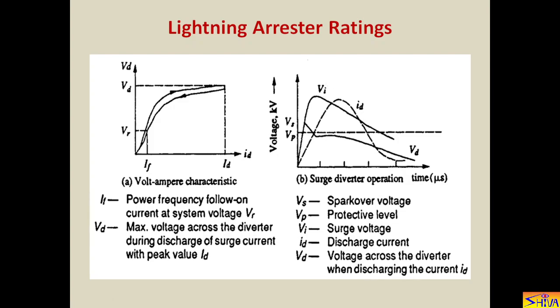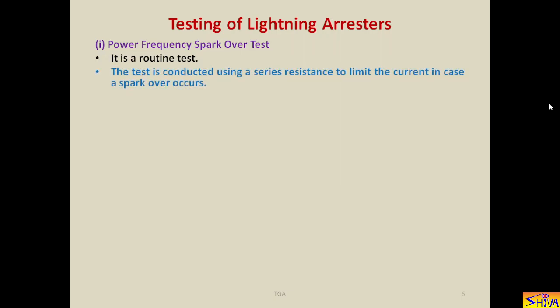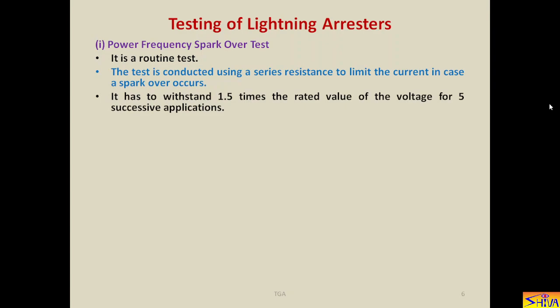So lightning arrestors are tested for power frequency spark over voltage, impulse spark over voltage, discharge voltage, and discharge current. So let us see what are the different tests. I have already explained or given you the names. Now let us see how these tests are performed on lightning arrestor. First test is power frequency spark over voltage test. It is a routine test. The test is conducted using a series resistance to limit the current in case a spark over occurs. So we are applying the voltage and connecting series resistance in order to limit the current.